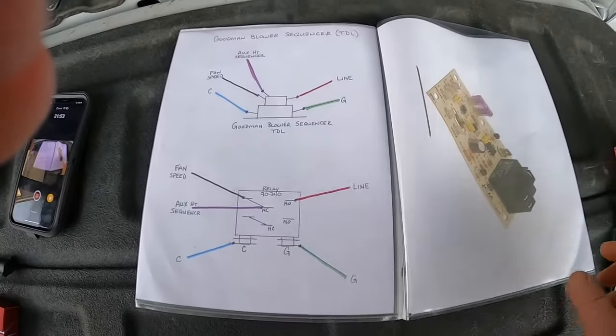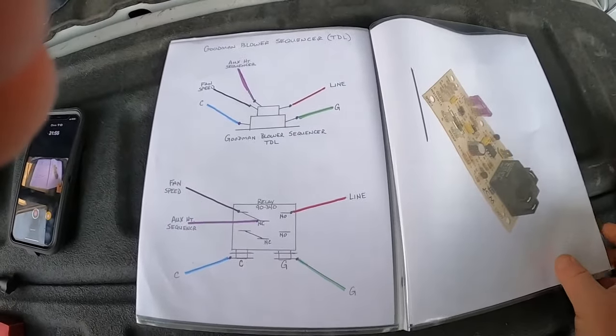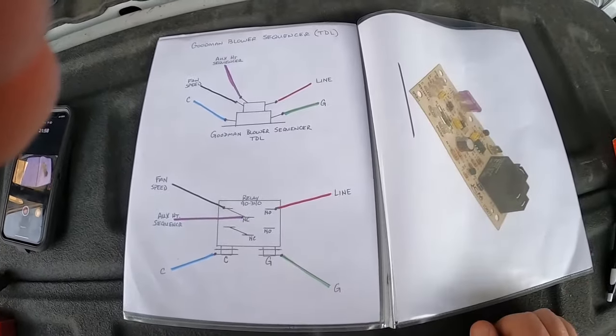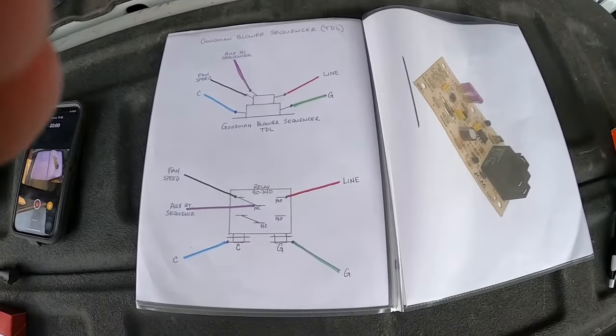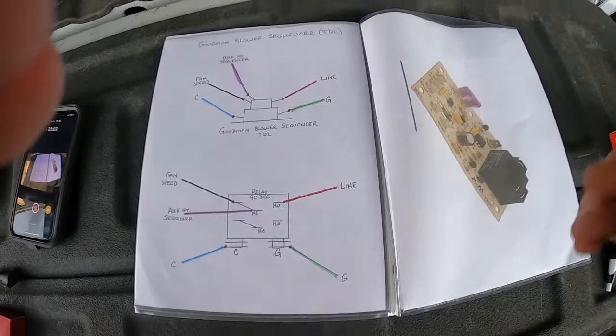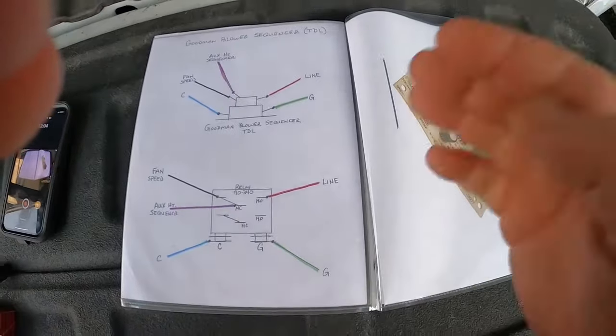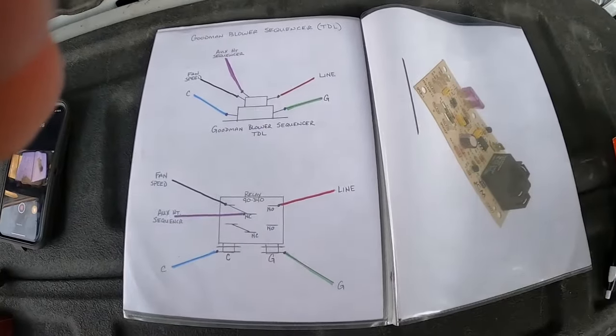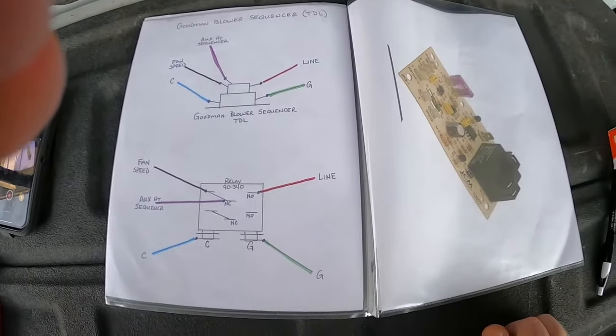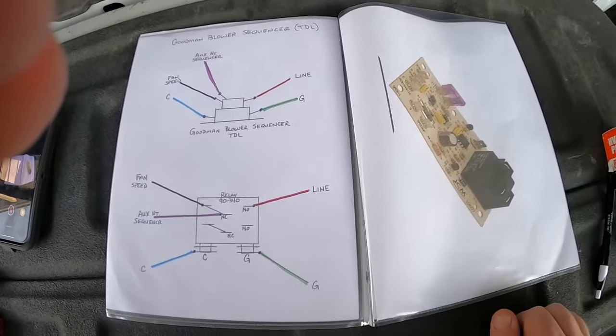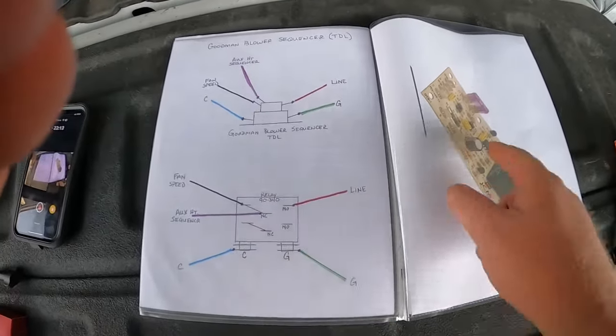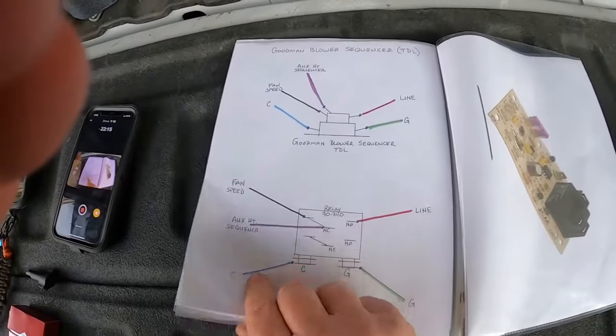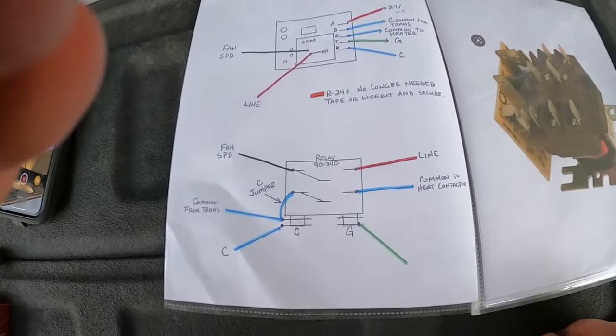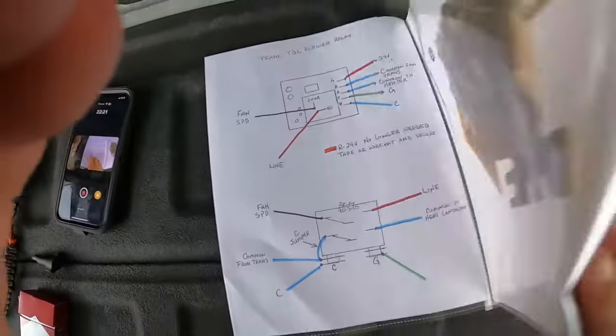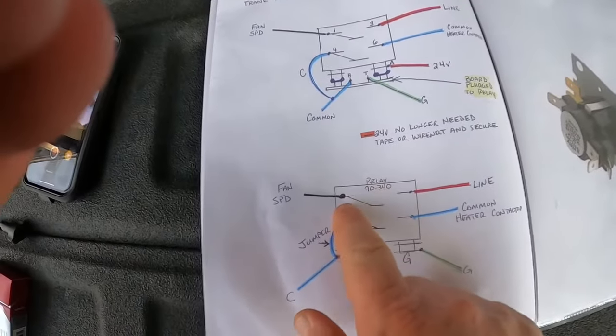Then you want to de-energize your heat strips, auxiliary, emergency, however you want to call it, and then make sure that once that sequencer opens and that last bank of heat strips cuts off, when your blower shuts off, you no longer have any amp draw on your heat strips. That's the best way to troubleshoot it. If you put one of these in and you try this and you put your disconnect in or turn your breaker back on and the blower comes on immediately, well, you've got something wired wrong.